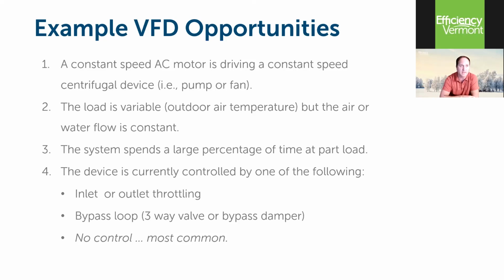We have a couple kitchen hoods that run at 2 speeds, and if the operators are diligent about running at the lower speed, they are observing some of the savings already. They're not getting the throttling or the modulating in between the high speed and low speed, but they are securing some of the savings. So those are some of the types of questions that we ask when we go into a project like that, because to the extent possible, we're trying to be very accurate with our savings forecasts. Our customers come to believe in the savings that we do forecast. They invest in projects accordingly. So, you know, we need to keep a high standard around that. Next slide, please.